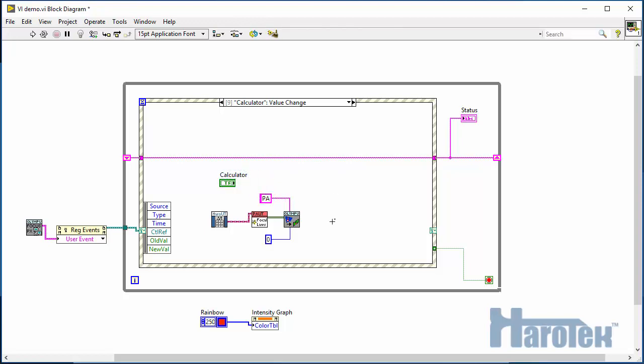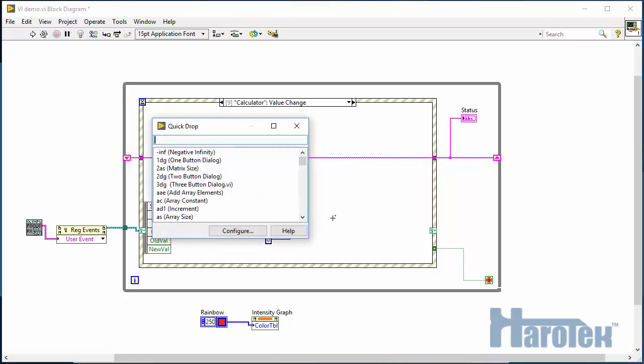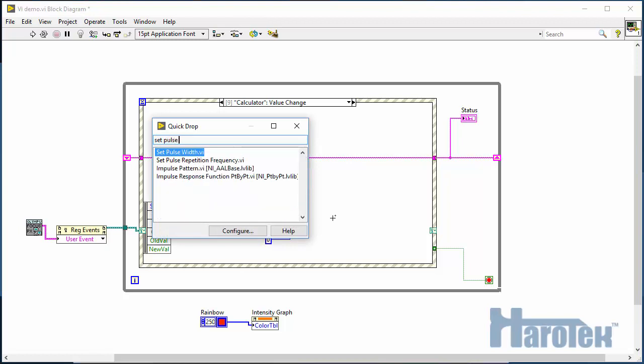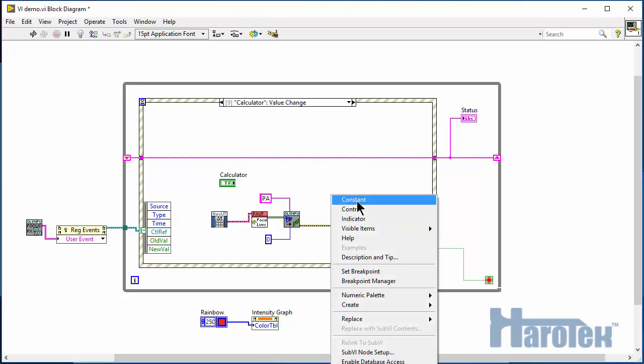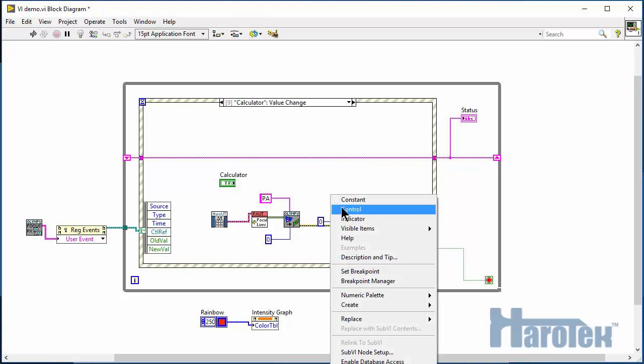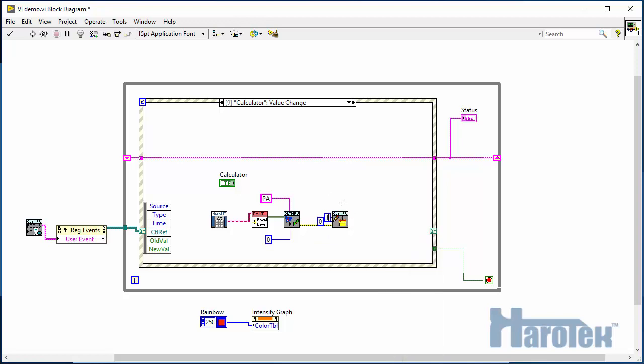After adding the phased array group, the excitation pulse width can be set to 100 nanoseconds. Once again, this is a parameter that could be made user changeable.